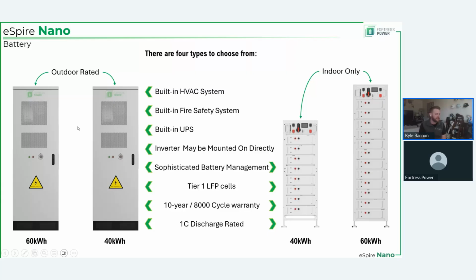Like I mentioned, the inverter can either be mounted on these outdoor cabinets themselves, or you can unistrut mount it. What you see on the right is the indoor-only option, but if I have to level with you guys, especially in California, you're not going to get this thing installed—there's too many hoops to jump through. If you're in an AHJ or utility that's more lax on its interpretation of the fire code around keeping batteries indoors, certainly we have the indoor option. But in my experience, 99% of our customers find it so much simpler to go with the outdoor rated solution, because it comes with fire suppression and an HVAC system to keep the batteries cool. For most customers it's a no-brainer—let's just go with the outdoor rated version. Not to say you can't put that indoors either.